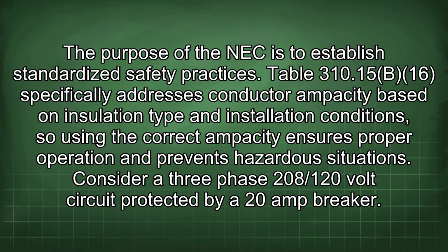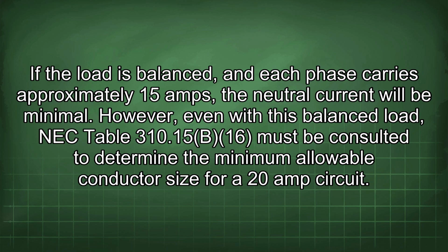Consider a 3-phase 208/120 volt circuit protected by a 20 amp breaker. If the load is balanced, and each phase carries approximately 15 amps, the neutral current will be minimal. However, even with this balanced load, NEC Table 310.15(B)(16) must be consulted to determine the minimum allowable conductor size for a 20 amp circuit.